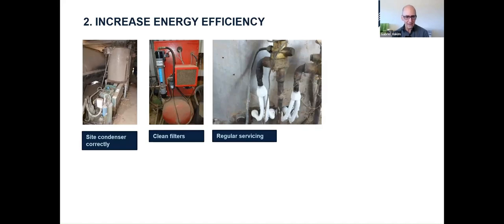Condensers. They're like a radiator, and they need lots of airflow to work. The condenser should always be positioned somewhere with unrestricted airflow, and usually somewhere shaded. This really applies when you're putting in a new system. If you can, place the condenser and the refrigeration unit somewhere shaded, usually on a south facing area, not in the sun, and somewhere that minimizes the amount of dust that will collect on the condenser fins. They're three areas that often get overlooked.